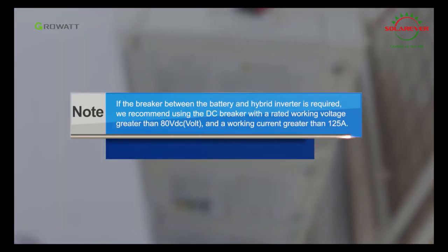Notice: if a breaker between the battery and hybrid inverter is required, we recommend using a DC breaker with a rated working voltage greater than 80 volts and a working current greater than 125 ampere.